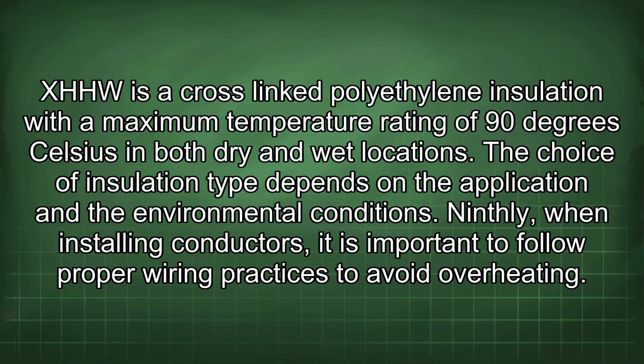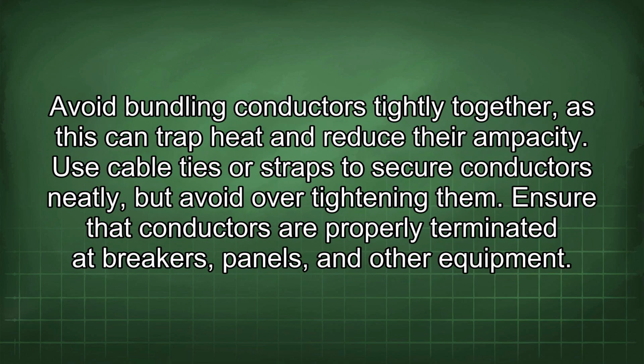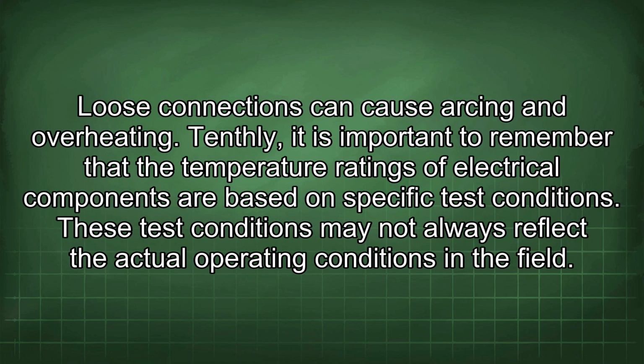Ninthly, when installing conductors, it is important to follow proper wiring practices to avoid overheating. Avoid bundling conductors tightly together, as this can trap heat and reduce their ampacity. Use cable ties or straps to secure conductors neatly, but avoid over-tightening them. Ensure that conductors are properly terminated at breakers, panels, and other equipment. Loose connections can cause arcing and overheating.